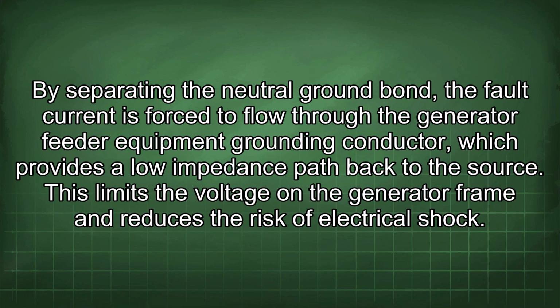By separating the neutral ground bond, the fault current is forced to flow through the generator feeder equipment grounding conductor, which provides a lower impedance path back to the source. This limits the voltage on the generator frame and reduces the risk of electrical shock.